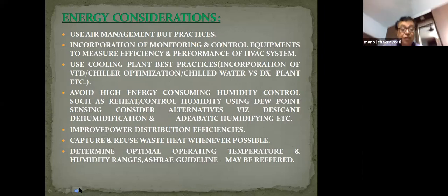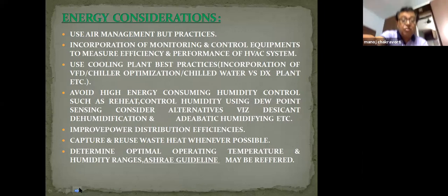Waste heat, whenever possible, we can use it. But waste heat is maximum in industry. When a data center comes up near industry, we can utilize the waste heat, because industry generates a lot of waste heat in the form of steam and so on. We can utilize this waste steam for air conditioning, for vapor absorption machines, where we can use the waste heat.